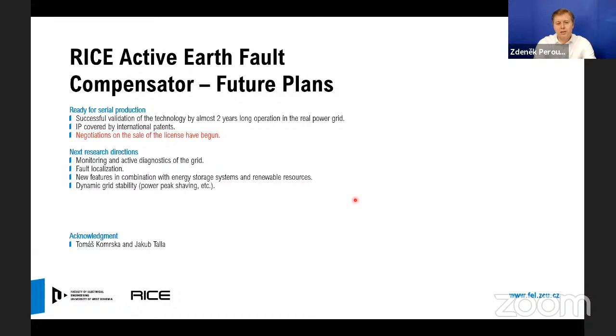The next research directions I see in new functions for the monitoring and active diagnostics of the grid. Specifically, we are working on fault localization using our device, which has already been implemented in our device, and we are now at the stage of field validation. And I see big potential in new features in combination of our device, of our current source, with an energy storage system or renewable resources, generally the combination of the power source with our device, which can bring new features, for example, for dynamic grid stability, such as peak power shaving, et cetera.